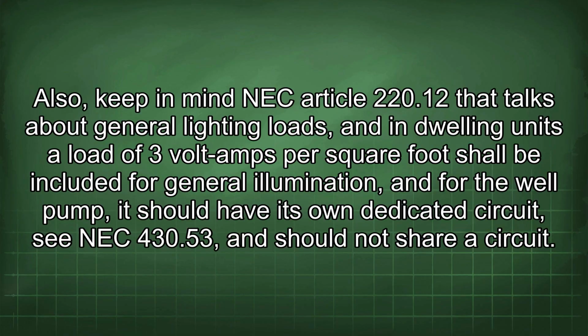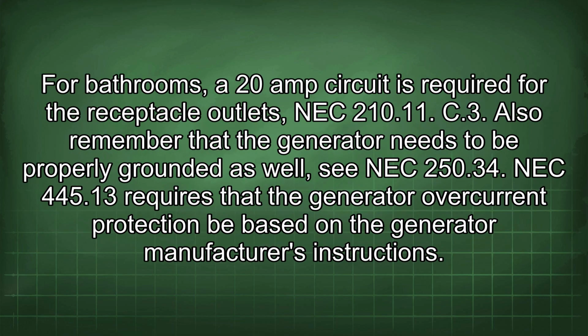Also, keep in mind NEC Article 220.12, which talks about general lighting loads, and in dwelling units a load of 3 volt-amps per square foot shall be included for general illumination. For the well pump, it should have its own dedicated circuit, see NEC 430.53, and should not share a circuit. For bathrooms, a 20 amp circuit is required for the receptacle outlets, NEC 210.11.C.3. Also remember that the generator needs to be properly grounded as well, see NEC 250.34.